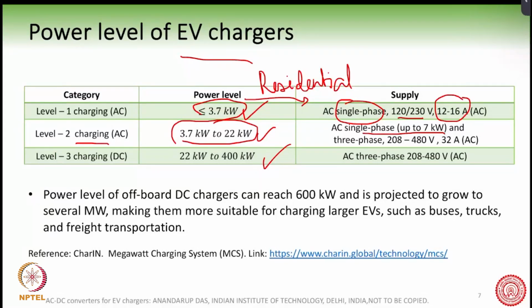The reason is that drawing a huge amount of power from one phase would unbalance the three phase grid, which the grid operator wants to avoid. So beyond a certain power, we must move to three phase systems, like the 400 volt three phase systems popular in India, which generally provide power up to around 22 kilowatt.